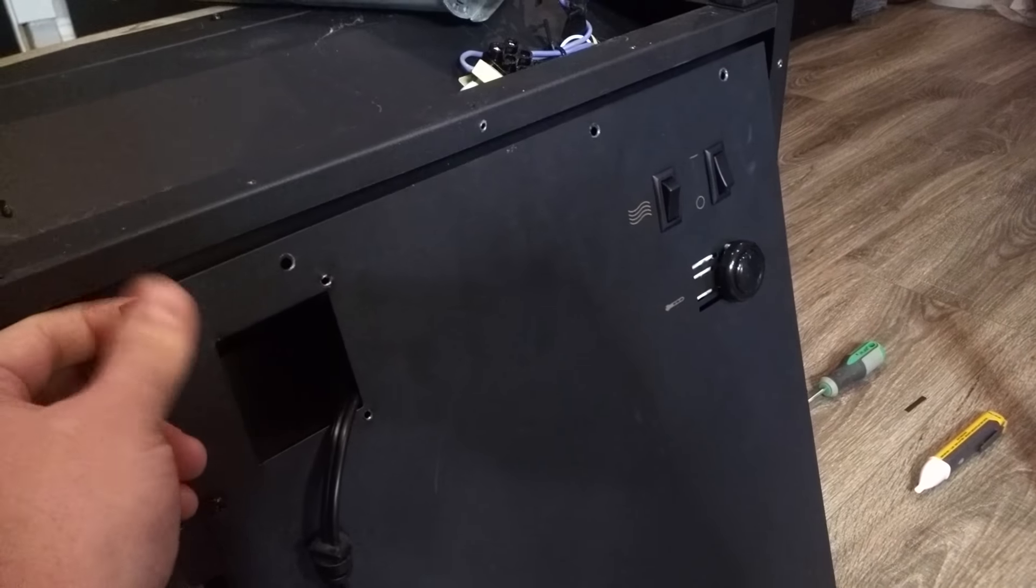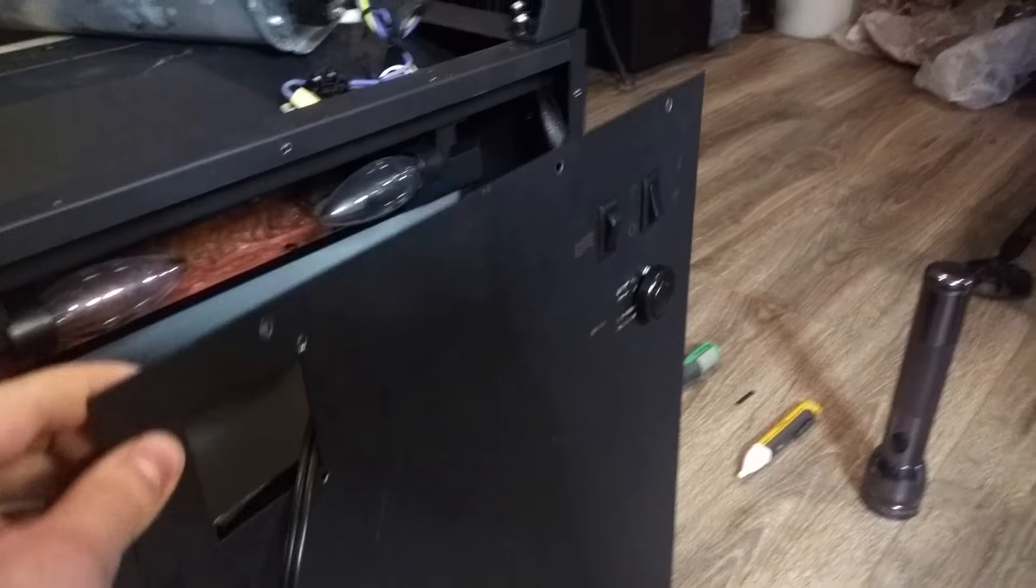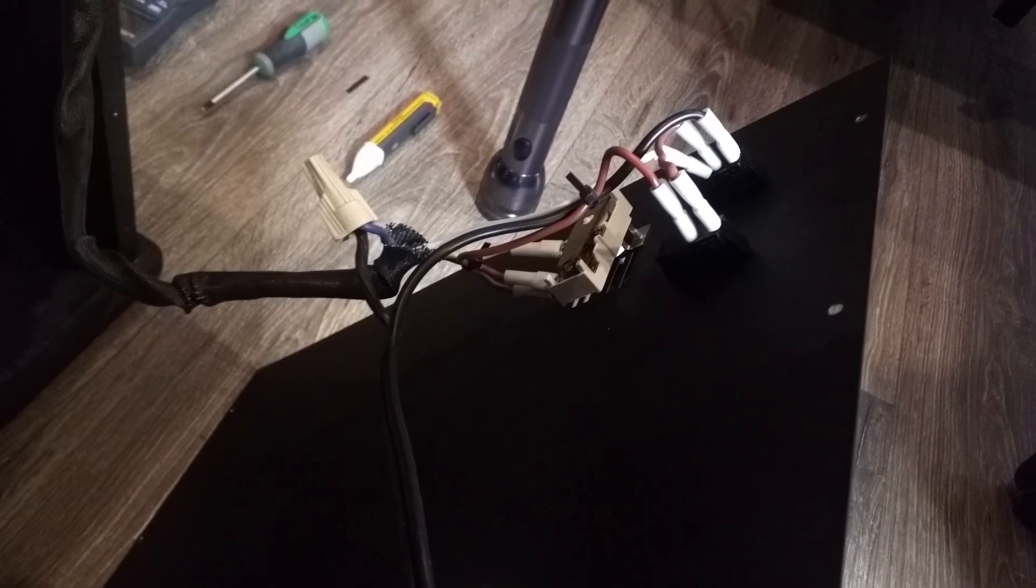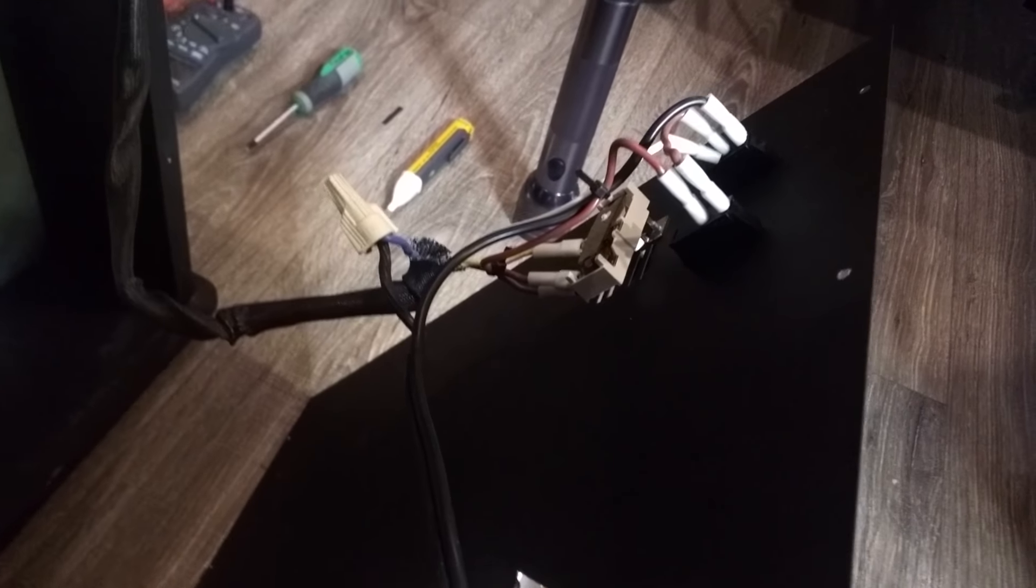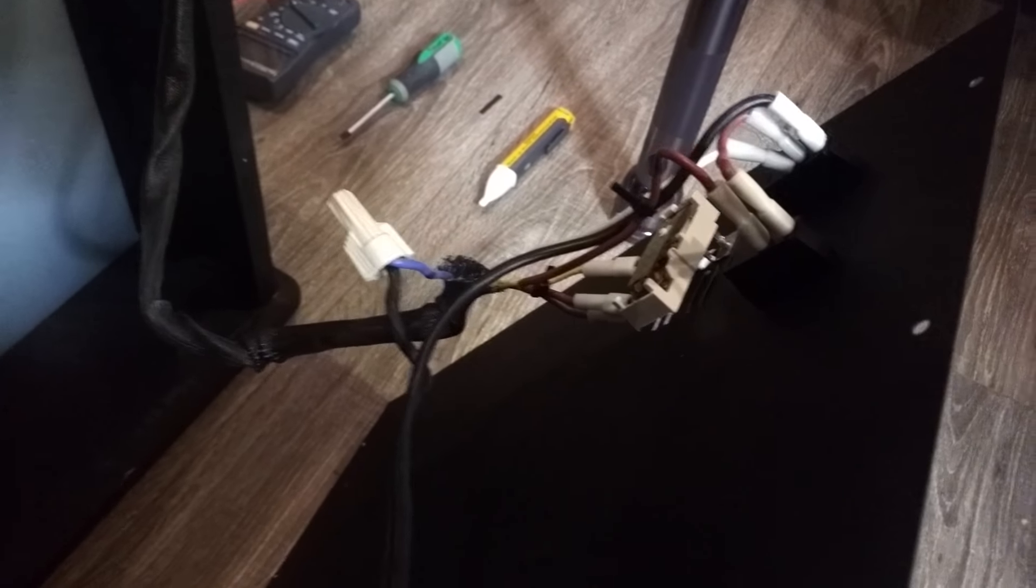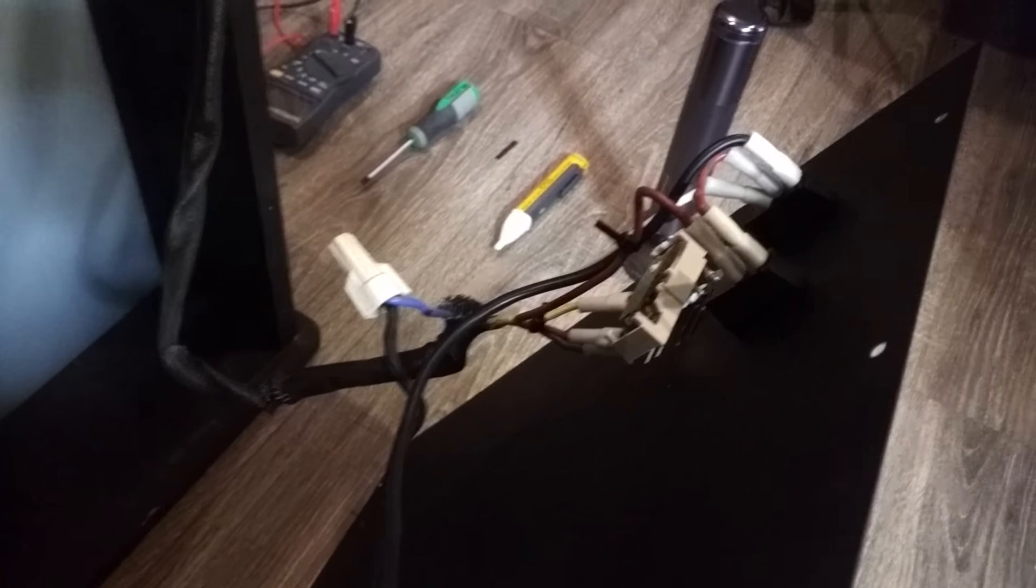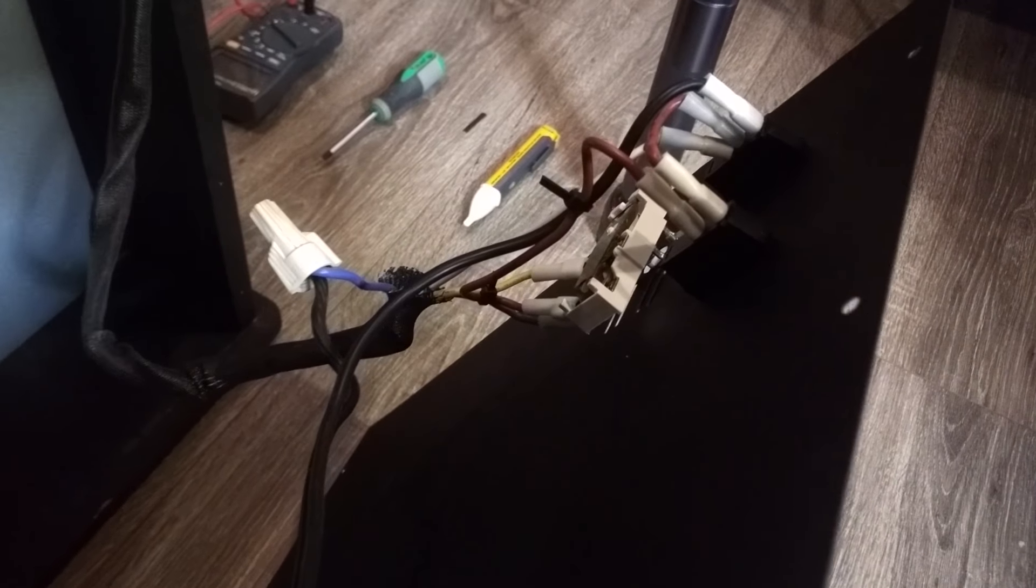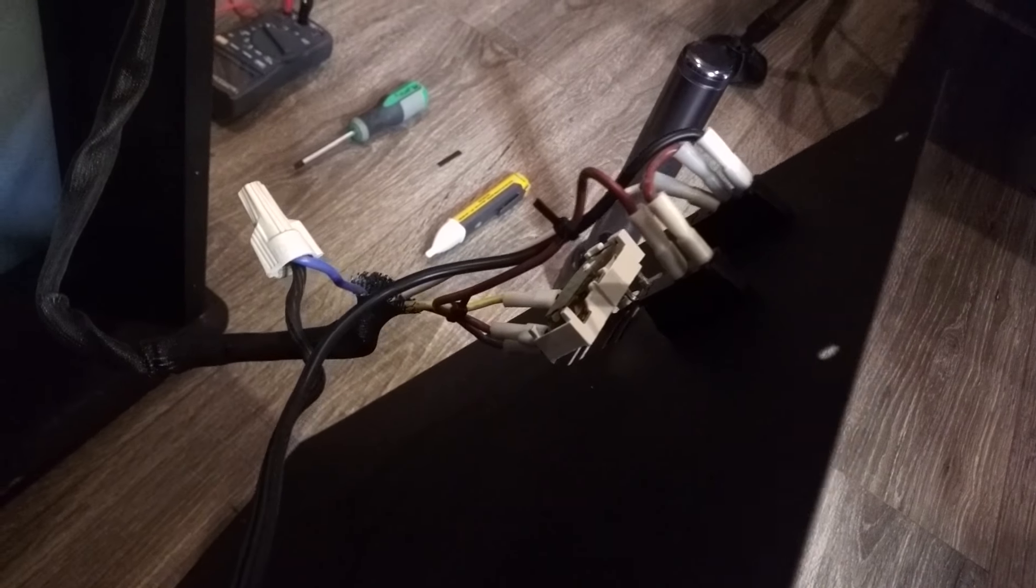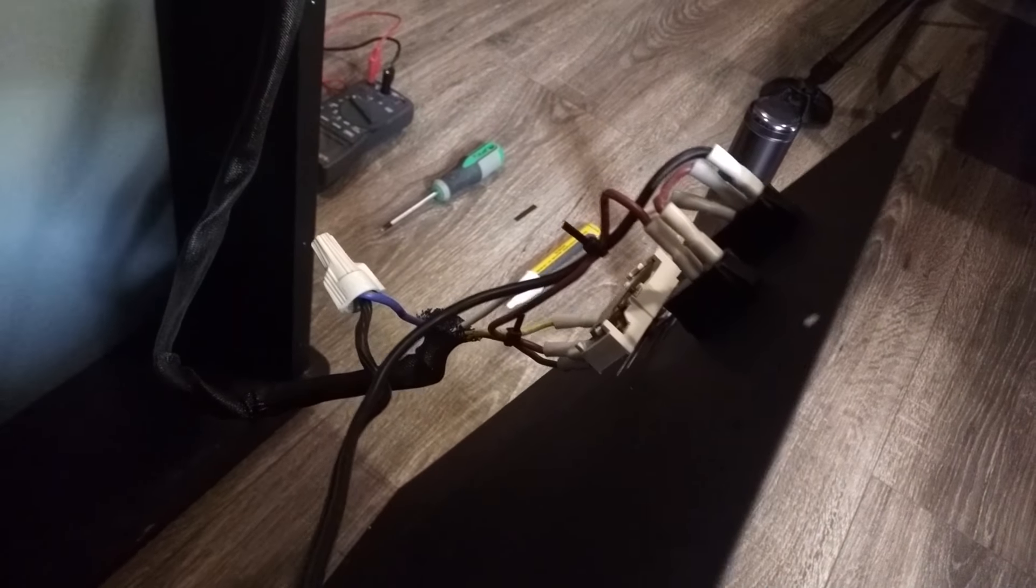I took off the back panel and started doing some continuity checks, just to make sure it wasn't a loose wire or anything. Here's the back of it. Up above are the switch connections, and down below is the thermostat. I turned the knob and did some continuity and resistance checks with the thermostat, and it seemed to be working fine. So that wasn't it.